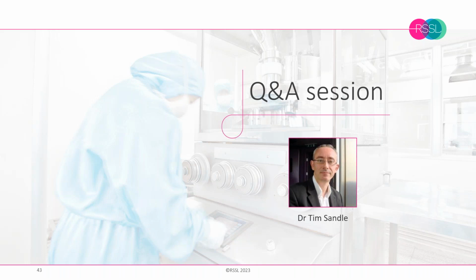So this is probably the last question we've got time for. It's from Annika, and she says, if you have a product that does not come into direct contact with equipment, is residue testing still necessary? Yes, but the residue would perhaps be more orientated towards the cleaning chemical, because obviously you still need to clean, and you've got to prove that you've got rid of traces of detergent or alkaline or acid-based chemical, but it might be something different that you're looking for, and that's important to build into the risk assessment before you undertake the cleaning validation.